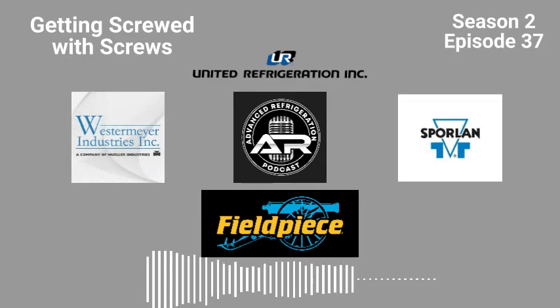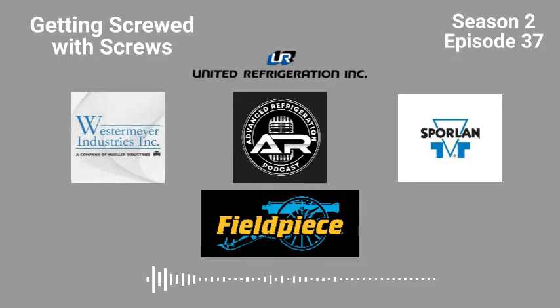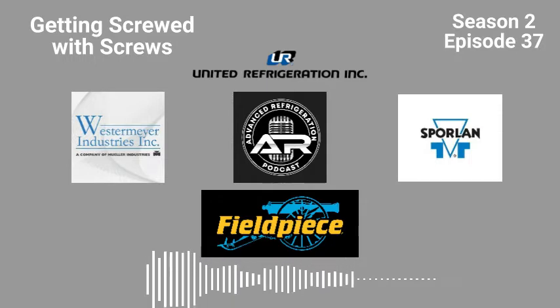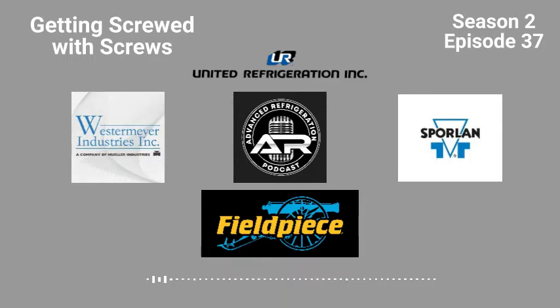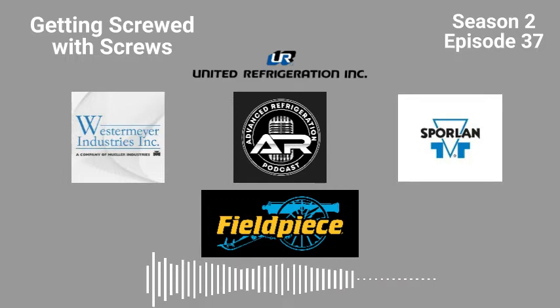Since I've been covered head to toe in 100 weight screw oil since 7 o'clock this morning. Oh, and screw oil is like molasses. How did that go? What happened? Oh, well, I went to go change an oil filter on a rack that got changed yesterday and blew out already. Holy shit. It wouldn't drain the oil out the bottom because the packed angle valve in the bottom was all plugged up. So I already knew where this was going. I already kind of just bit the bullet and accepted my fate that I was going to take an oil bath today at some point.